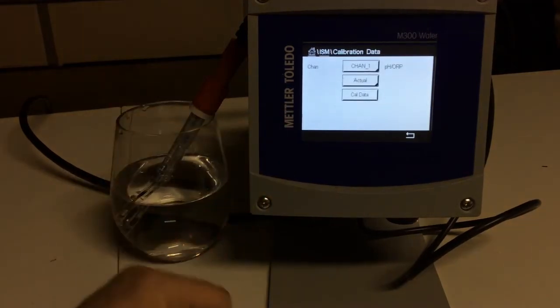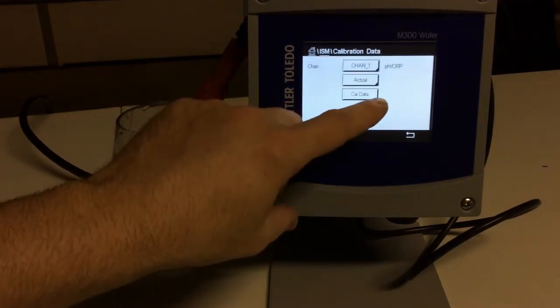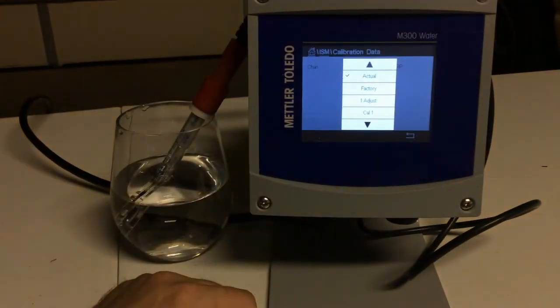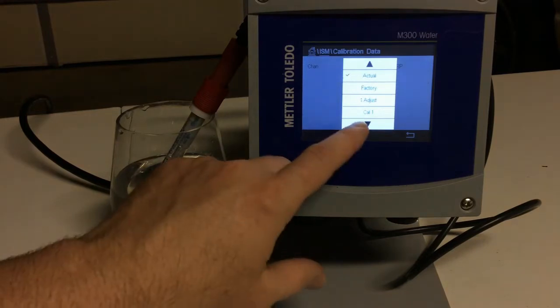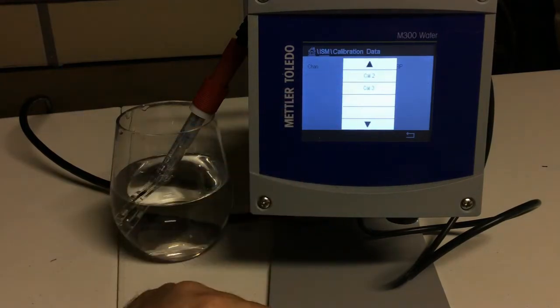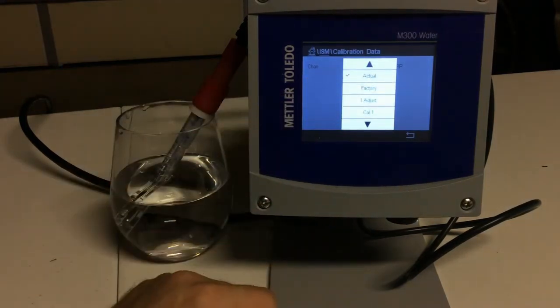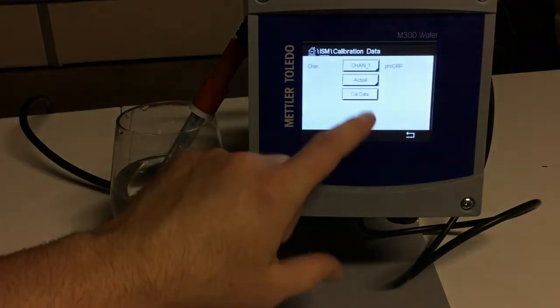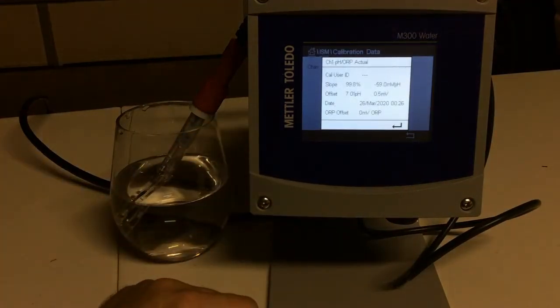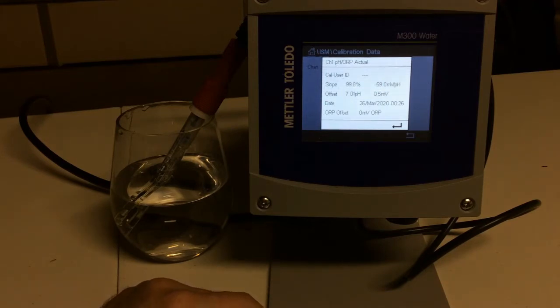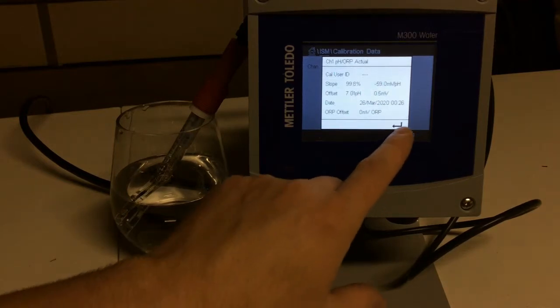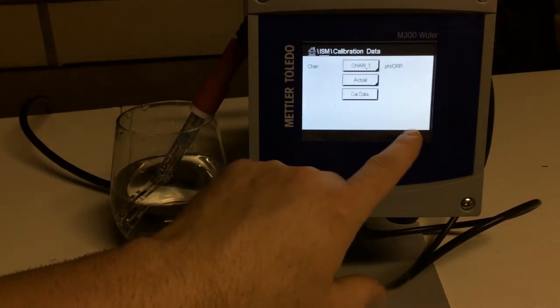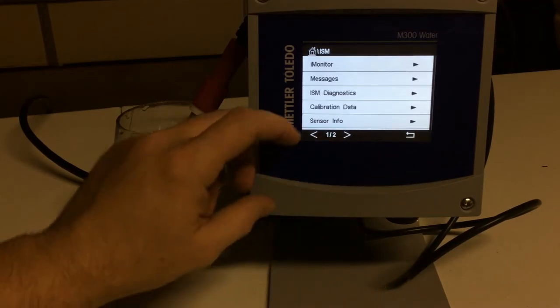So, and that is with the ISM Diagnostics Cal data. This will save up to five different Cal data for you, so we can see what our actual Cal is, what it is right now. If we wanted to go see our factory Cal, we can do that. But then, if we wanted to see our last three Cal's, we can look at all that information. If we look at our actual Cal, we can see this was calibrated on March 26th, which I did yesterday. And we can see what our slope was, what our offset was, and so forth. Really nice information so you know when it was calibrated and get some information.